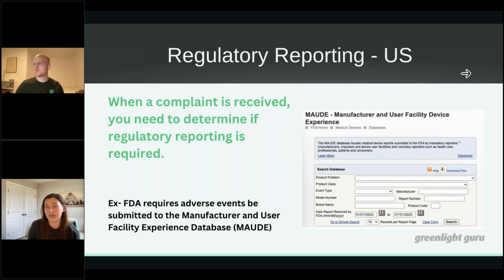But for the FDA, if you determine that reporting is required, you do have to submit those adverse events to the MAUDE database, which stands for Manufacturer and User Facility Device Experience. And something that I always like to point out when I talk about the MAUDE database is the fact it's manufacturer and user facility. So things can get reported here that you may never have heard about.